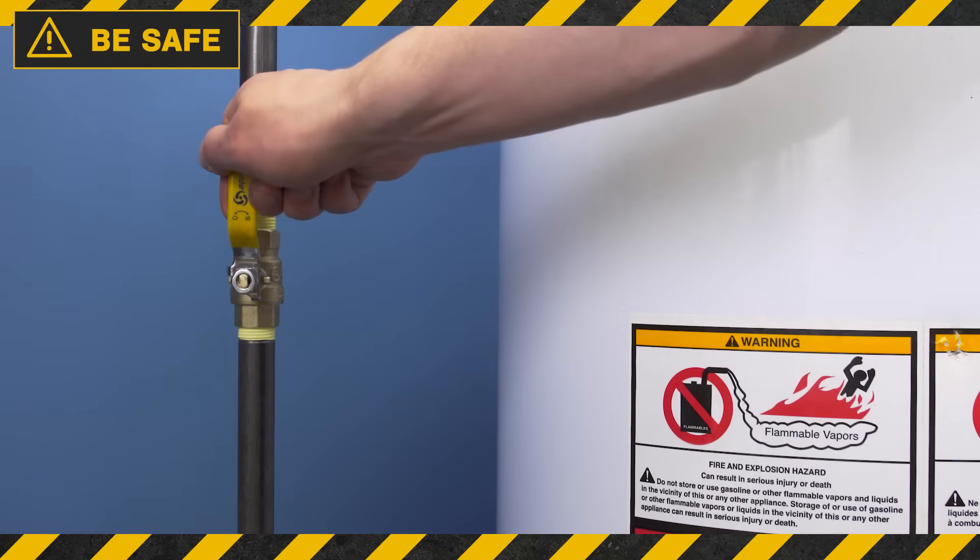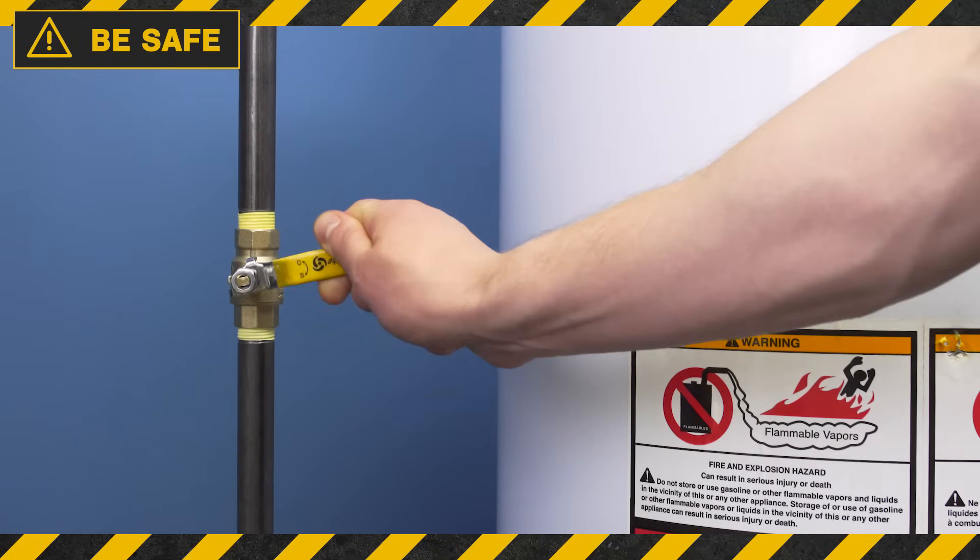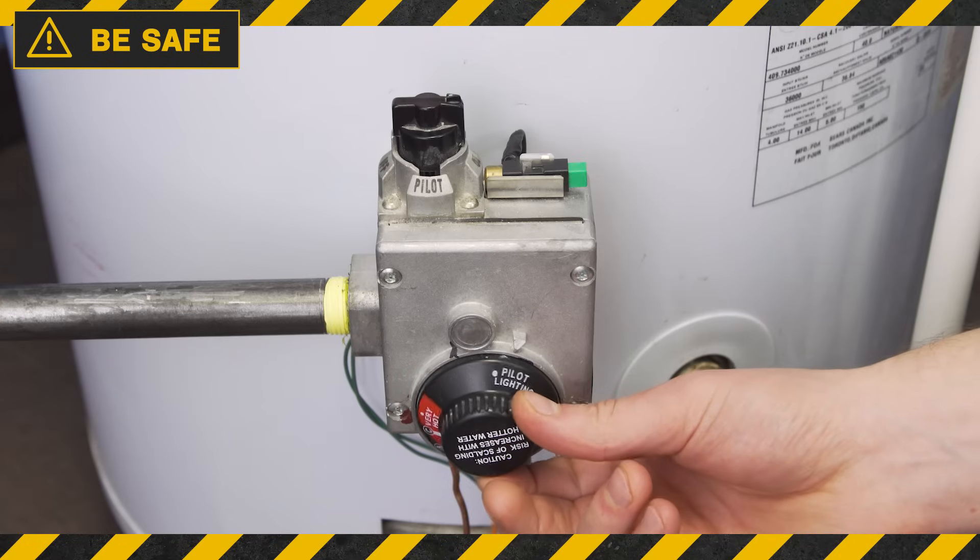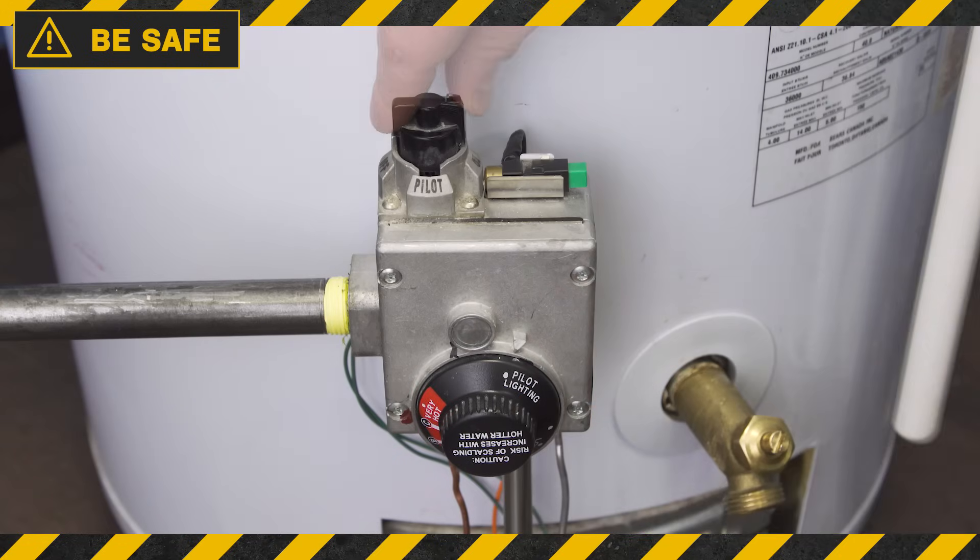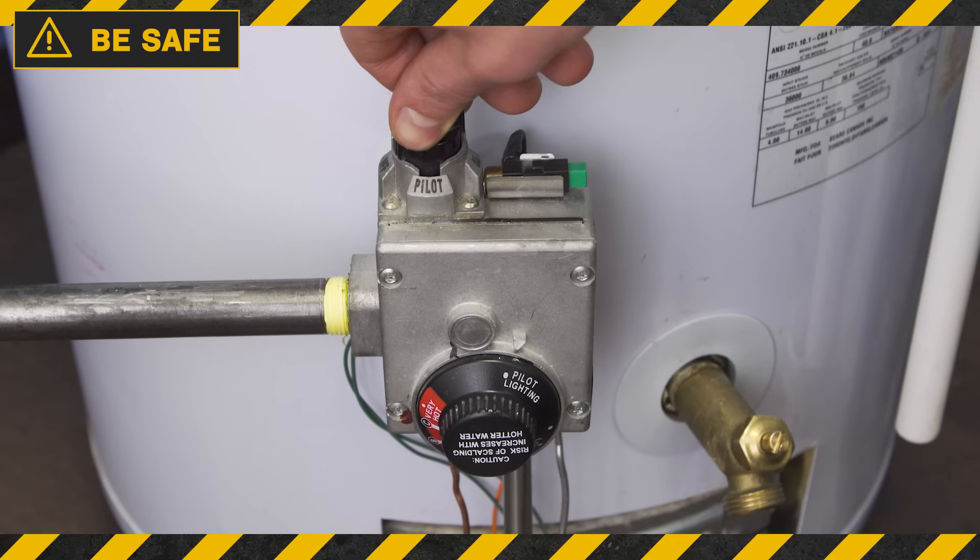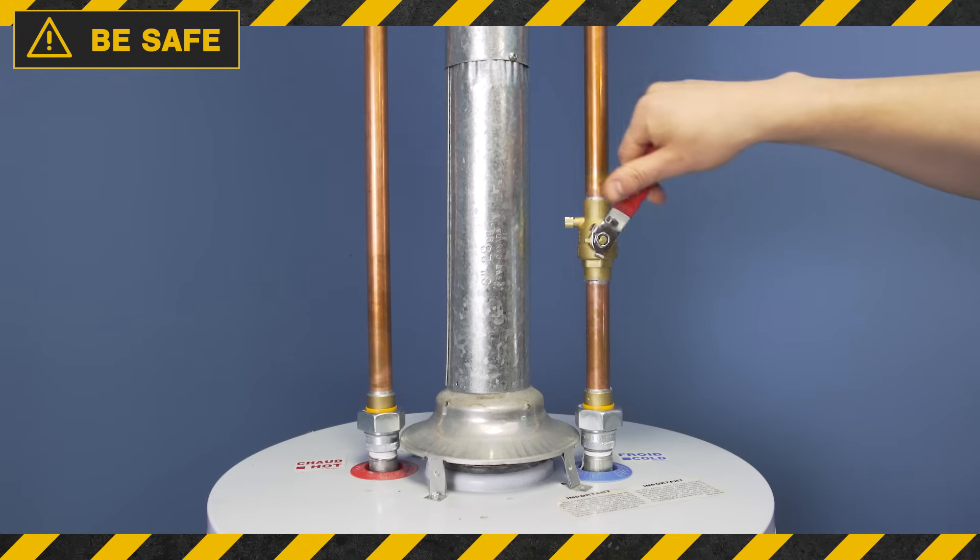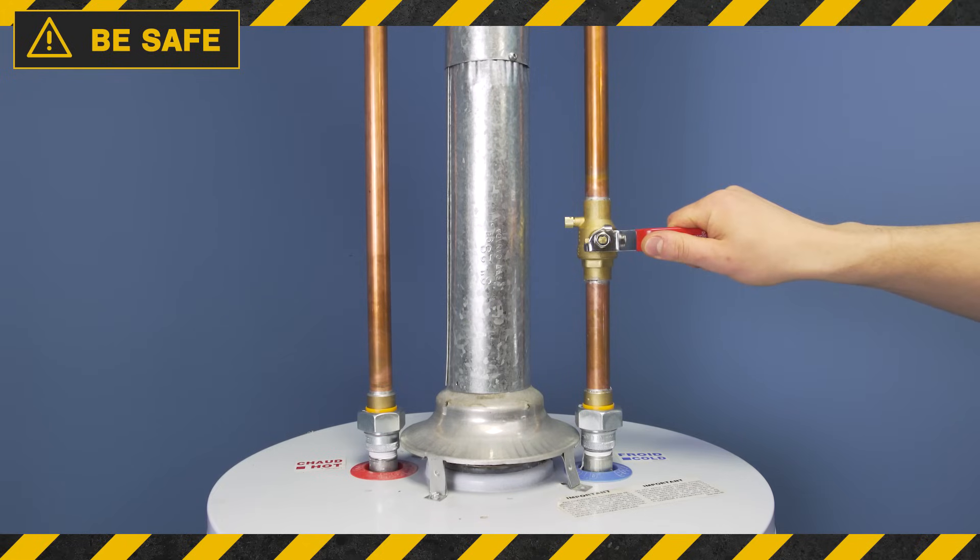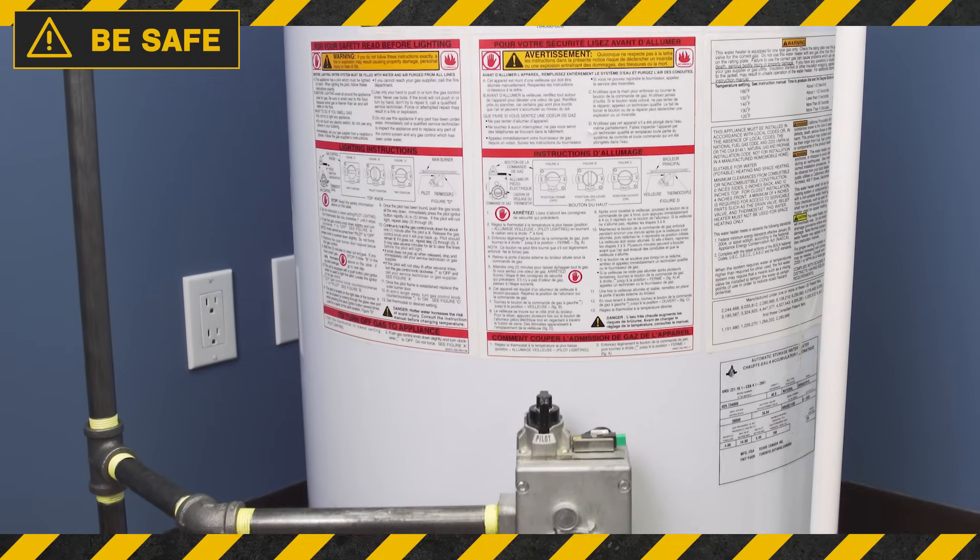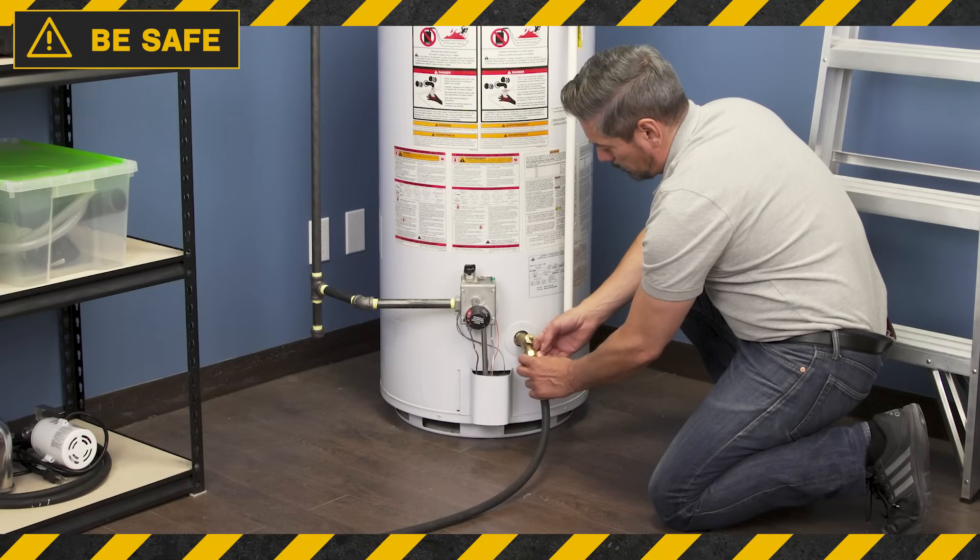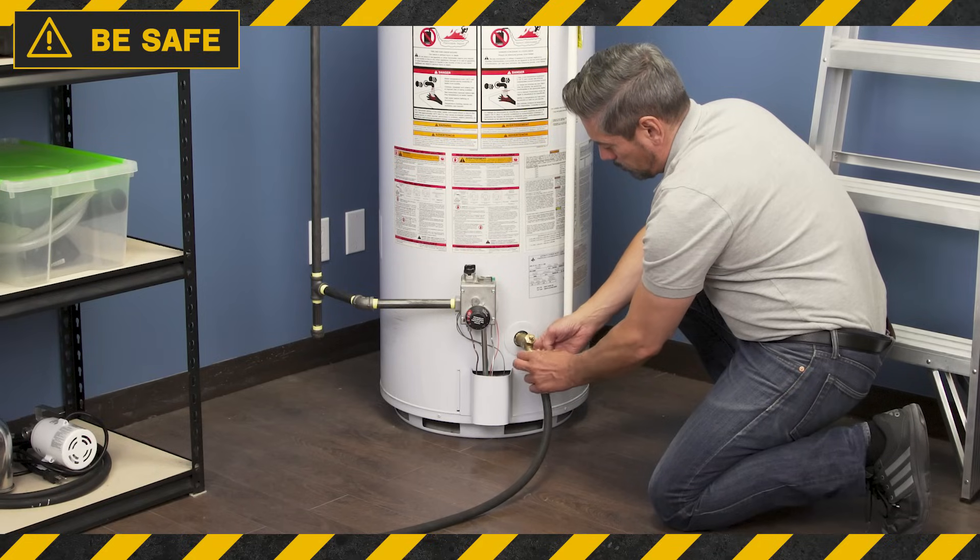First turn the gas supply off, or perpendicular to the pipe. Now set the water heater to the pilot setting, and turn the gas control off. Next shut off the cold supply. Keep in mind that the water inside the tank is still hot, so use caution when draining or accessing the tank.